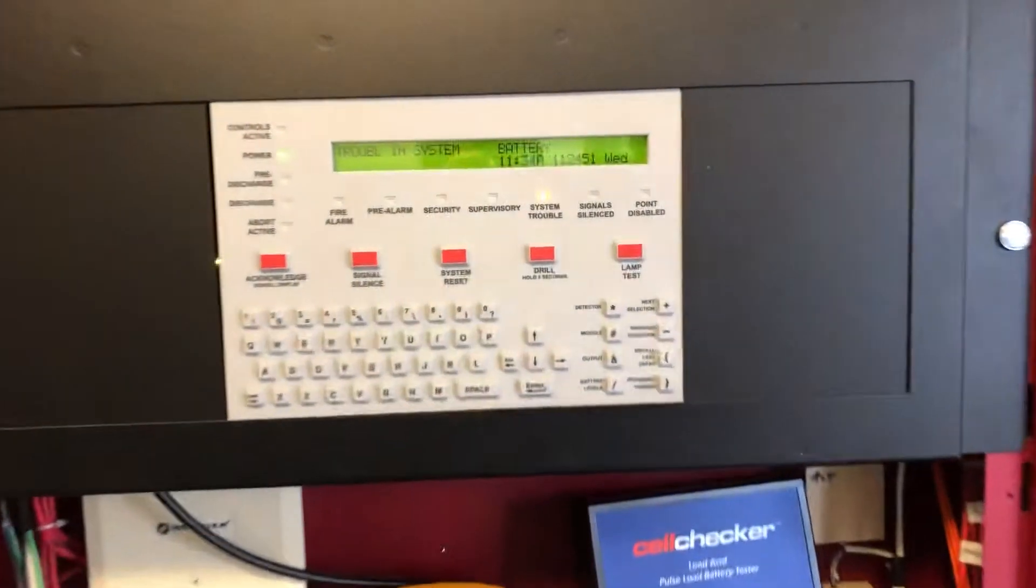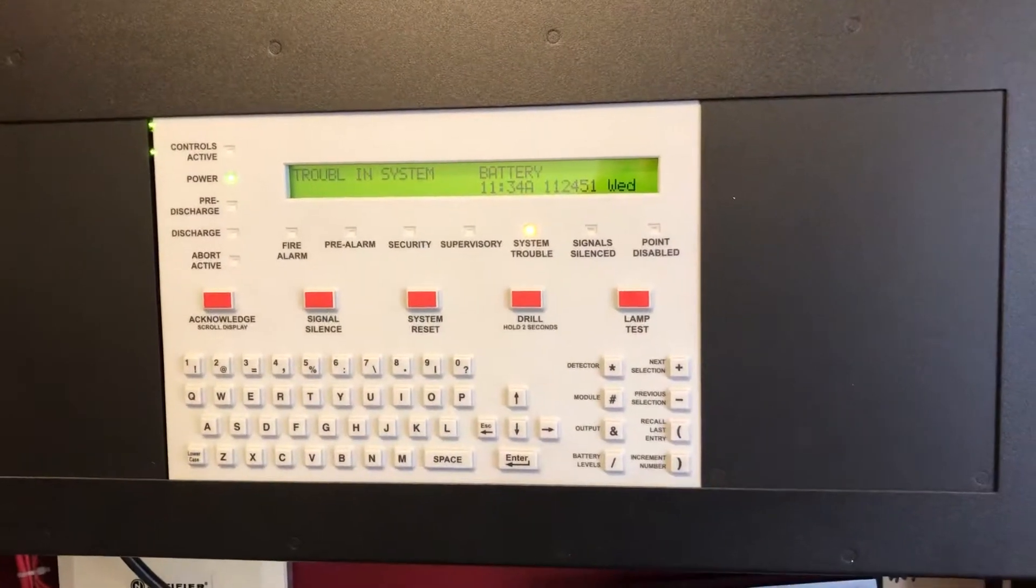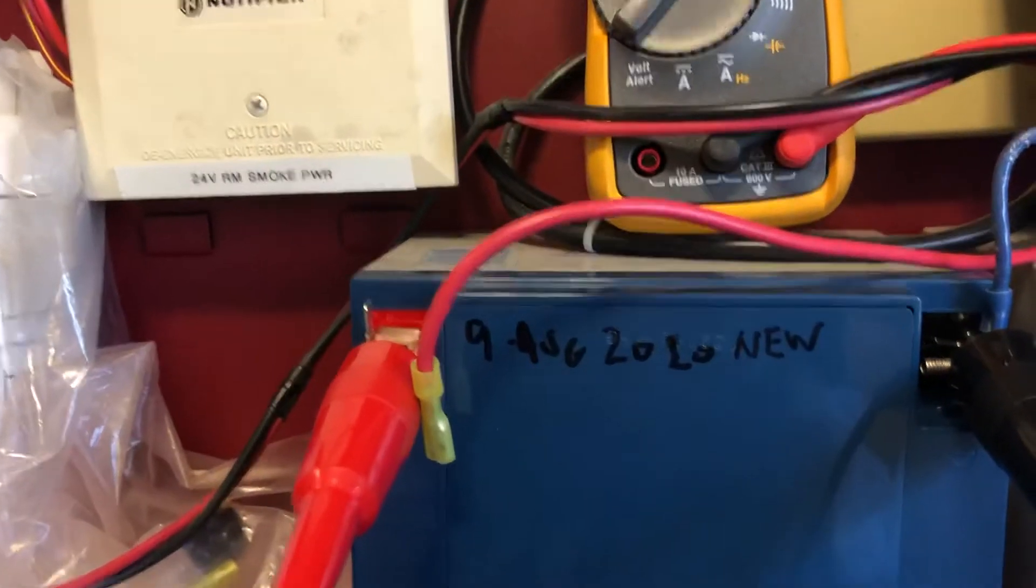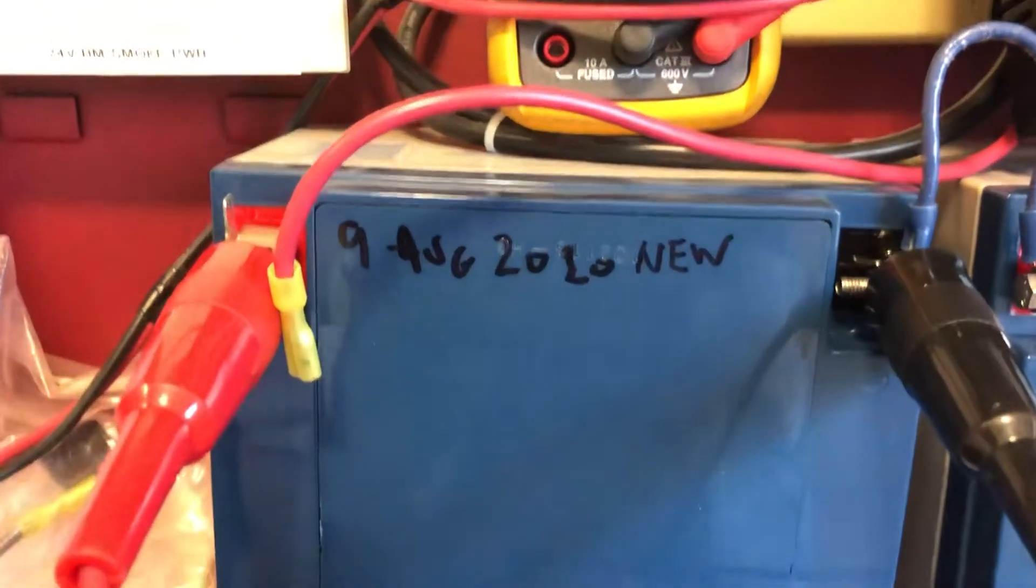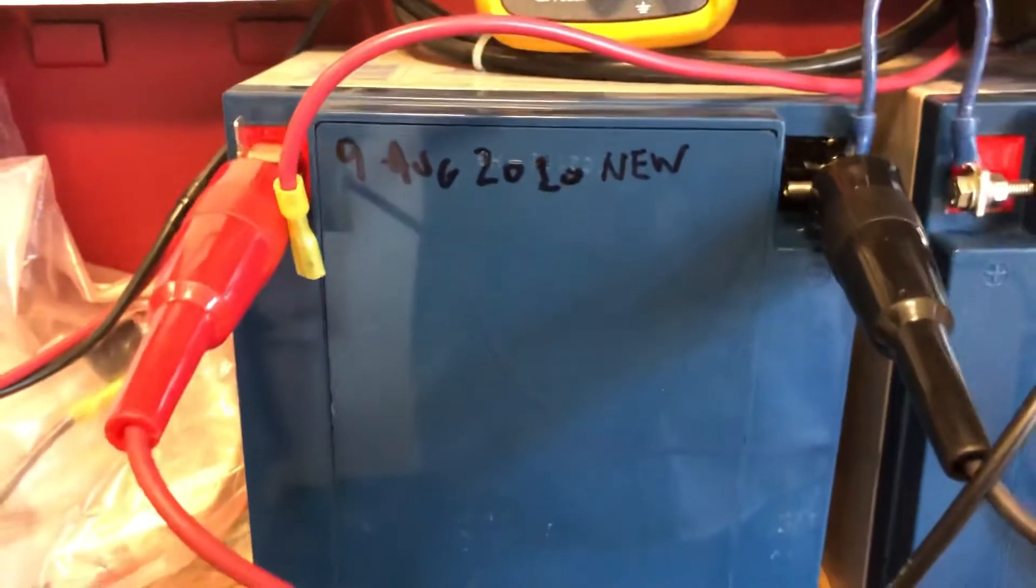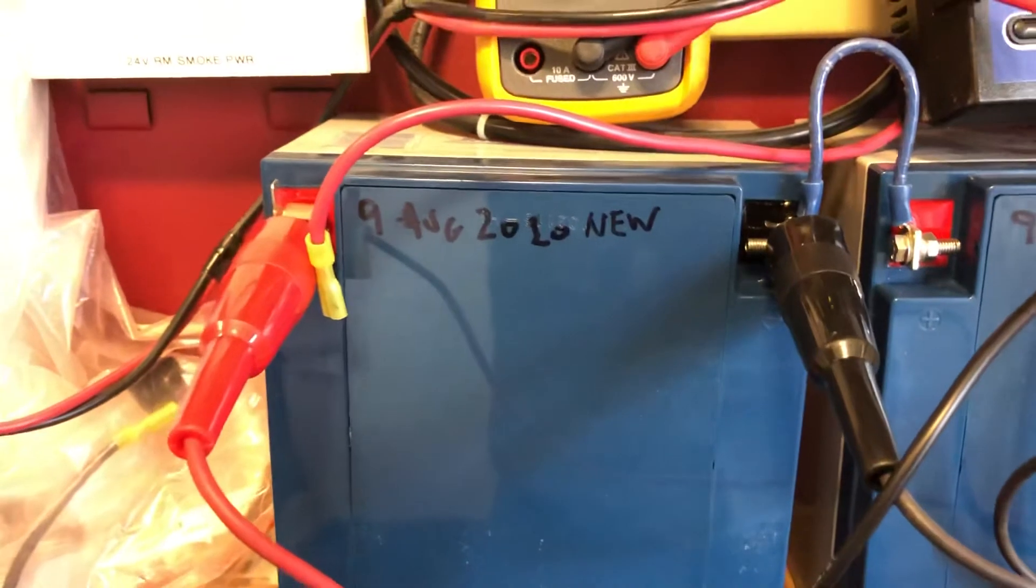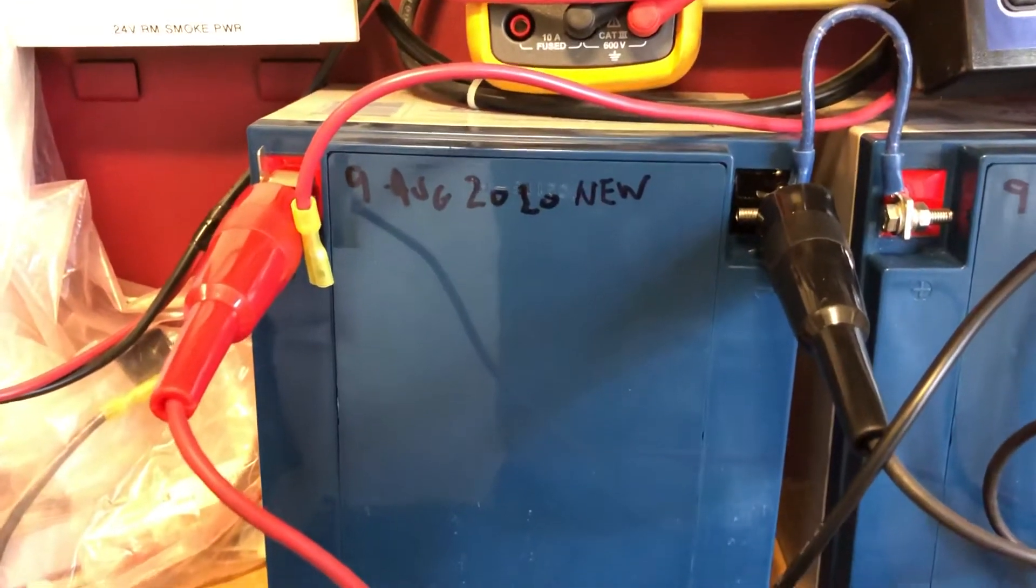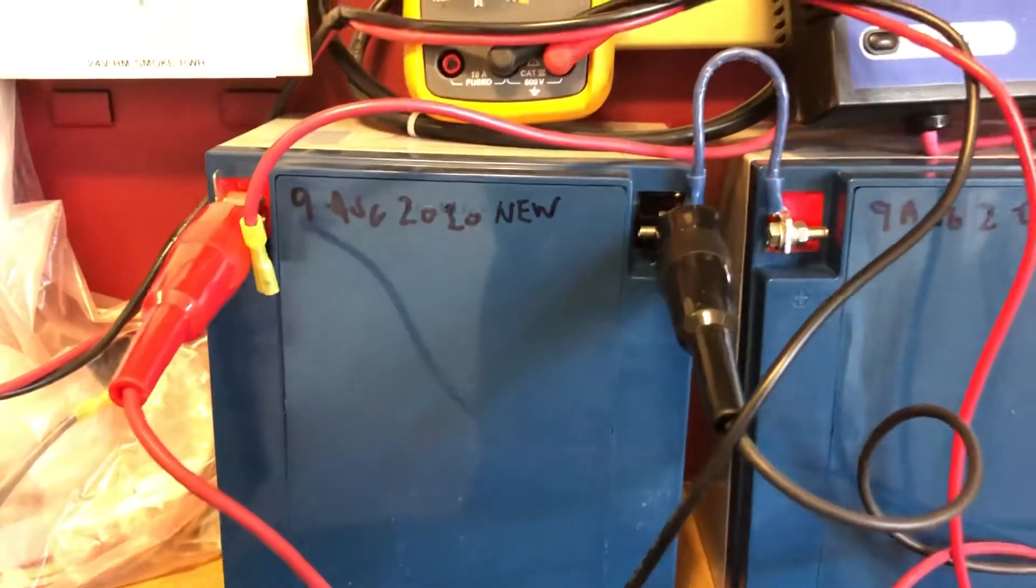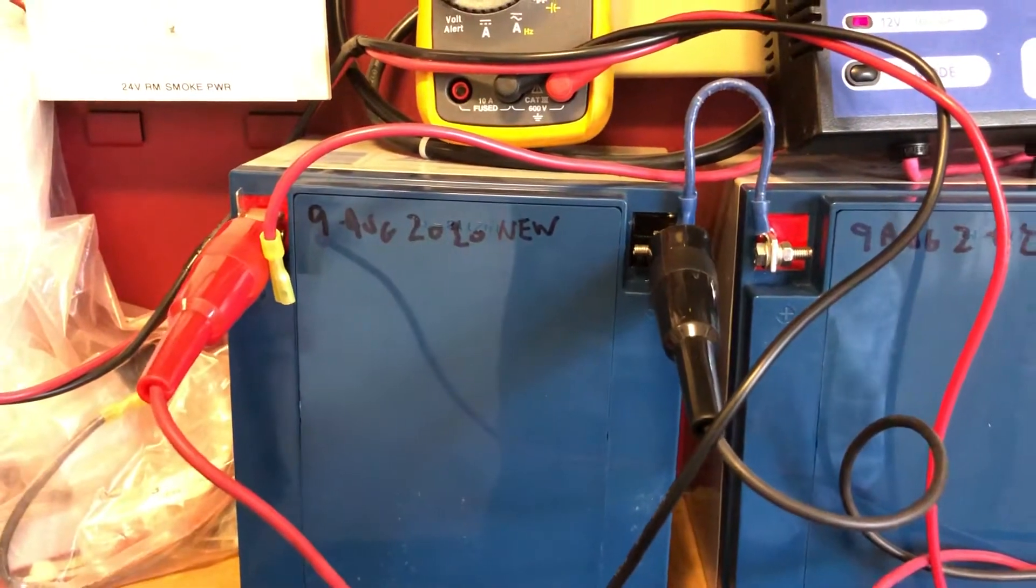This is an NFS2 640. The battery was replaced just last August 9th, 2020. It was replaced a year previously as well, and for some reason the batteries were not holding a charge.